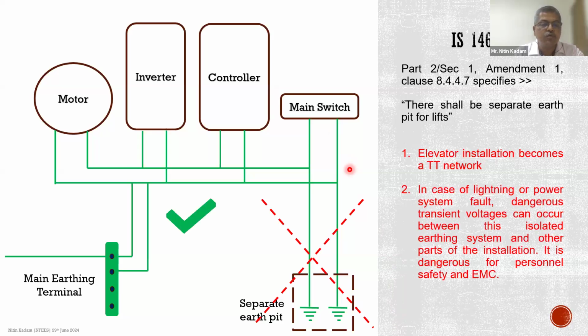The right approach is to connect the separate earthing from the MET terminal to the equipment, that is, the motor, inverter, controller and the main switch. And from there, you also take it to the other parts in the elevator installation. In case of a TN network, this goes back to the secondary of the transformer, from the star point of the transformer, from where you have a separate earthing coming to the installation. But in case of a TT network, it is a local earth on the site, and this MET terminal is connected to the local earth on the site. So this is the right way to do the earthing on site.